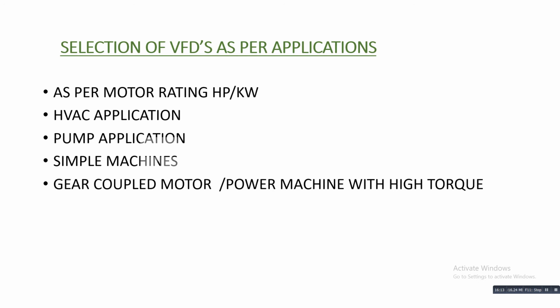Then the application. What kind of application are you going to use it for? HVAC. HVAC means heating, ventilation, air conditioning application. Then pump application. If your equipment is a pump, a water pump or any pump, you can select the pump application. The next one is simple machines. Then gear coupled motors and power machines with high torque. If your equipment is a gear coupled motor or a heavy power machine where you need high torque for starting, this VFD is available in all these categories. So whenever you are selecting or purchasing a VFD, you have to make sure of all these things: the main ratings and then the application.